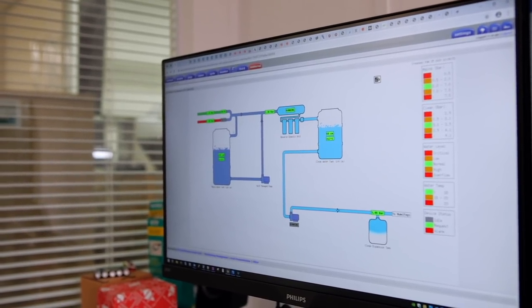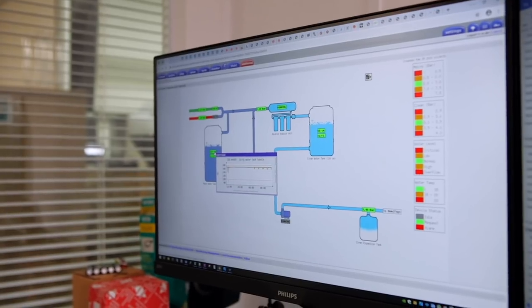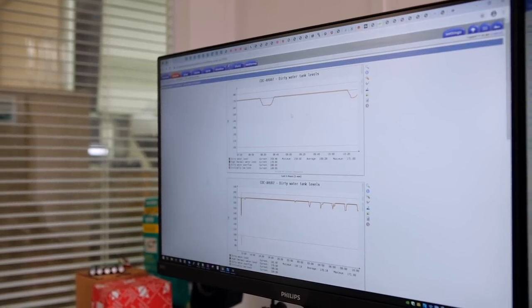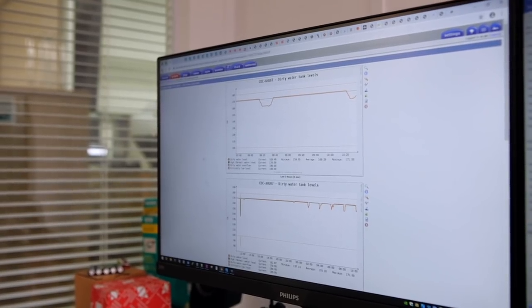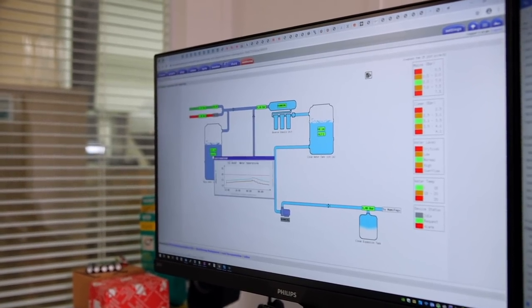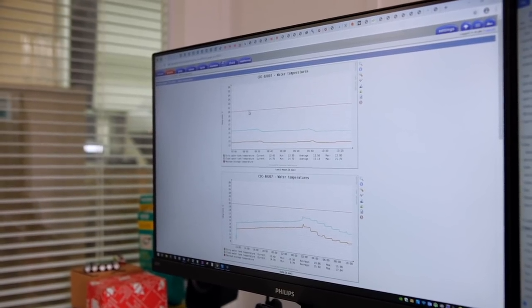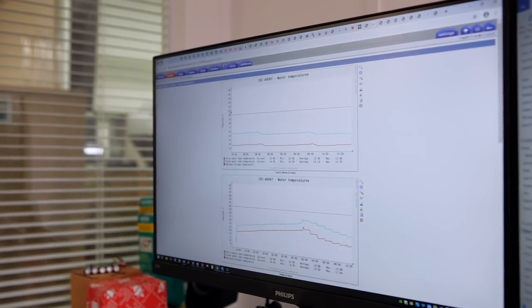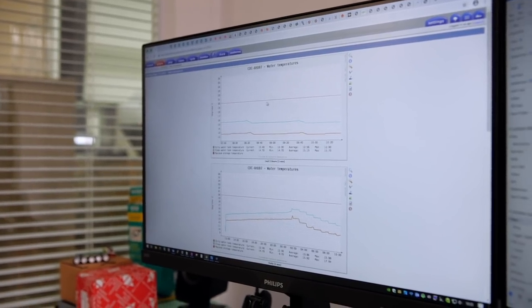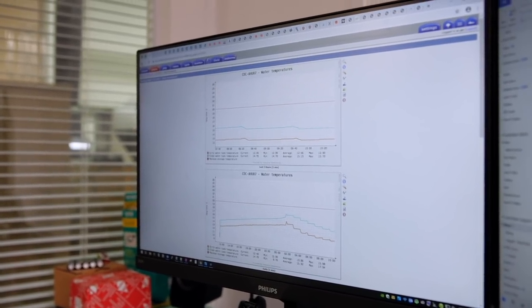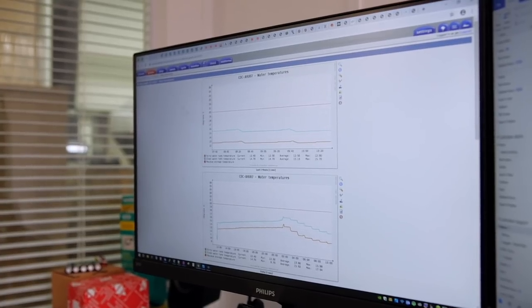Then we have a water level in the actual pre-clean water tank. As you can see from the history, it dips slightly because it's being used by the cleaning system. Temperatures of both tanks—you can never store water above 20 degrees because of Legionella risk, so we have to monitor this quite closely. Should this cross that line, we would have to either chill the water or just drain it.